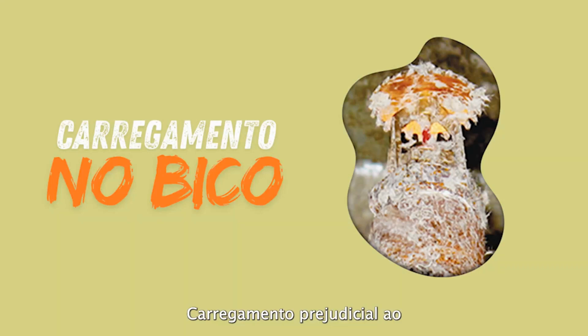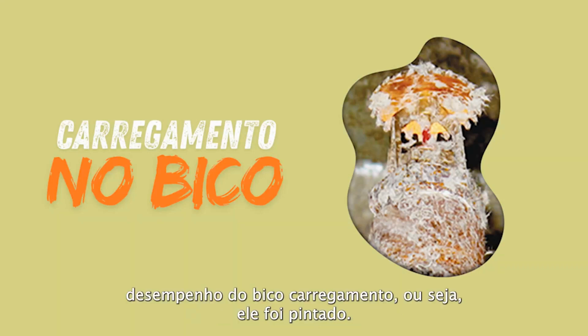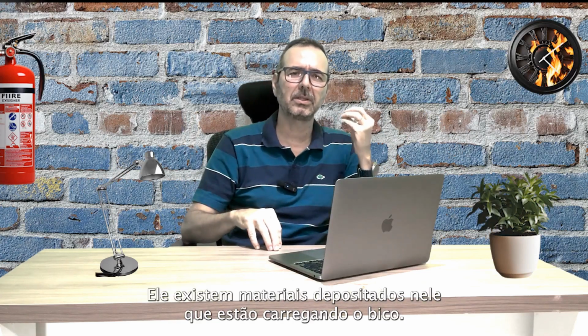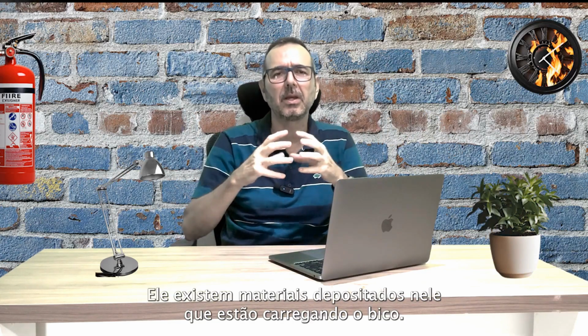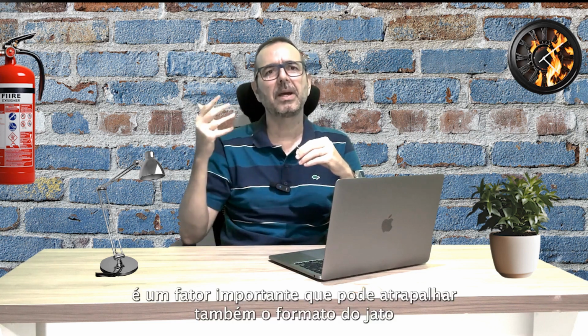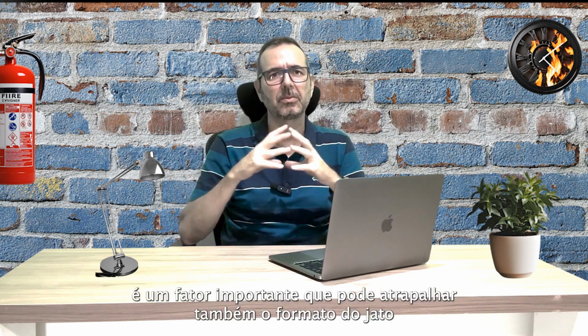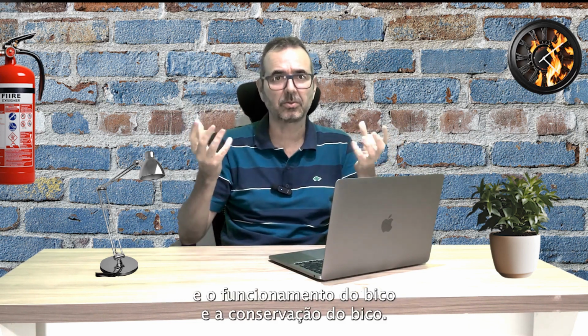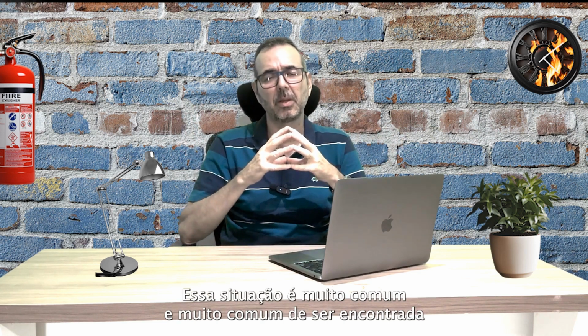Loading that is detrimental to the performance of the nozzle. Loading, meaning it has been painted, or there are materials deposited on it that are affecting the nozzle. Any type of mechanical or physical interference with the nozzle is an important factor that can also disrupt the shape of the spray and the functioning of the nozzle, as well as the maintenance of the nozzle. This situation is very commonly found during the annual visual inspections of the automatic sprinkler system.